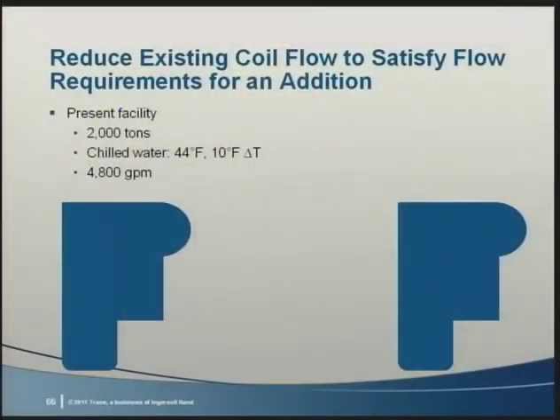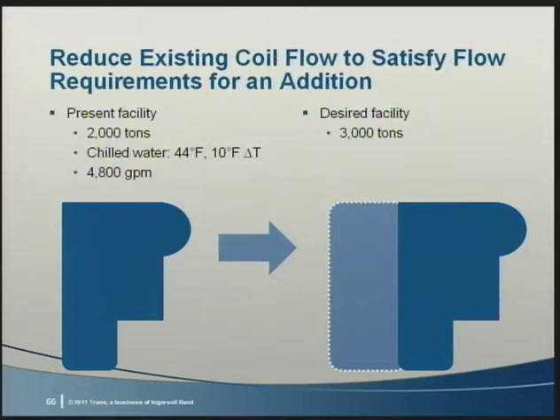It worked very well in a healthcare facility in Opelika, Alabama, as well as other projects. They had an existing hospital and clinic that had been added to over the years. It was time for another addition, but this time it was a big one. They needed to expand the facility from 2,000 to 3,000 tons. The existing coils at design conditions used 4,800 GPM, 44-degree chilled water, and a 10-degree temperature difference.